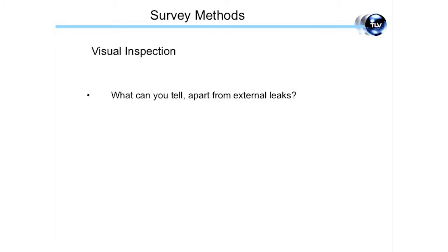What I would like to do is just touch on some different testing methods to highlight reasons for using, I'll say the best, but the more comprehensive systems. Some people say, well, we can just look at the trap and tell whether it's working or not. I'm very impressed. Most traps have an inlet pipe and an outlet pipe. Unless there's steam actually coming physically out of the trap body, I don't know how you're going to tell anything. But some people still say that's the best way.